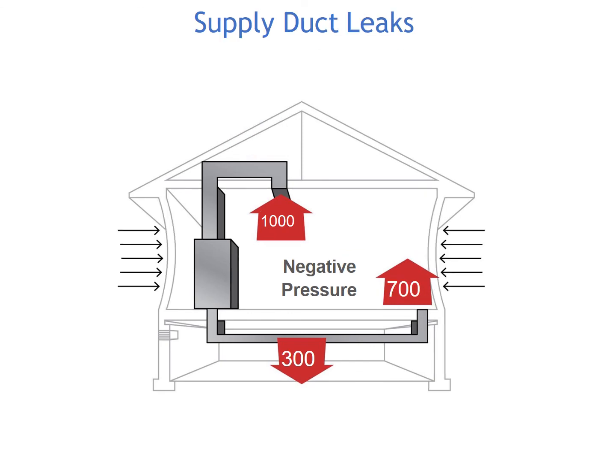This illustration shows a perfect example of what happens when you have supply duct leaks. If you have 1,000 CFM, 1,000 basketballs, going into the return side of the unit, 1,000 has got to come out the other side of it. It's going to automatically push it out. But if you're losing 300 of those into the basement and you're only putting 700 CFM, or 700 basketballs, back into the house itself, the system's still going to pull in another 1,000. So where's that going to come from? It's got to come from somewhere.